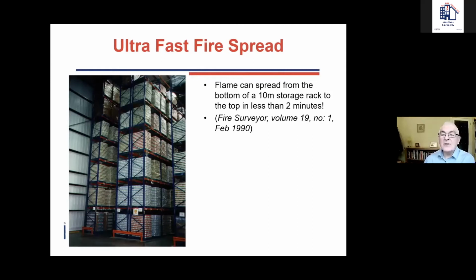If you take nothing else away from this session today, think of this: a flame can spread from the bottom of a 10-metre storage rack to the top in less than two minutes. Just think about that - less than two minutes. So even if you have smoke detection, that's going to take perhaps a few seconds to activate, and then it takes time for people to recognise the fire alarm's gone off and decide what to do. By that time, the fire is out of control.